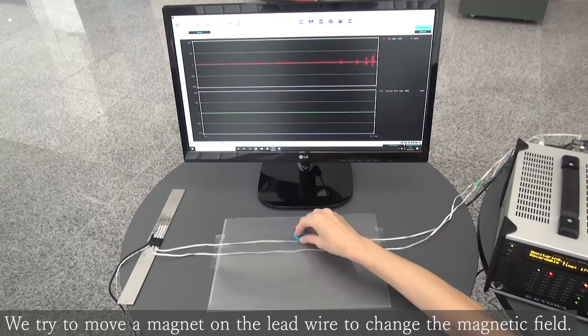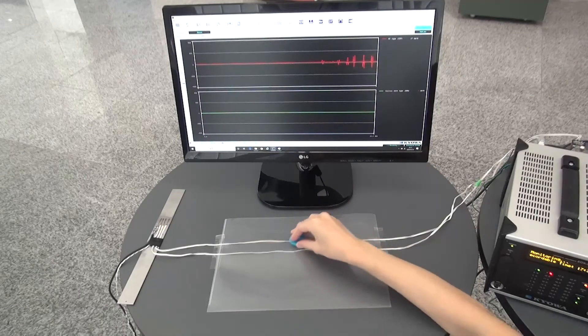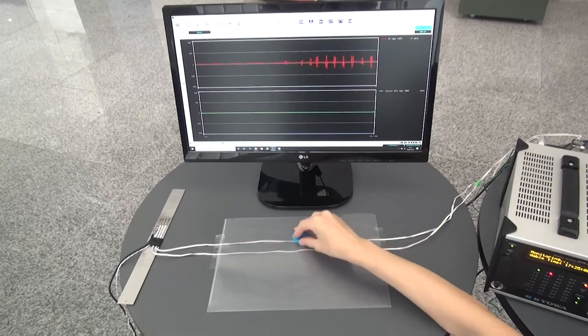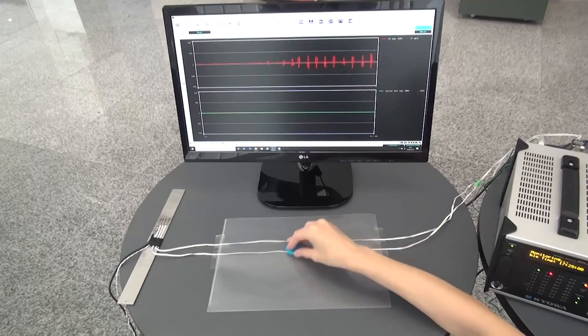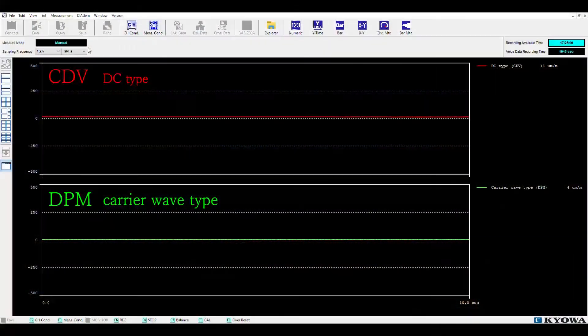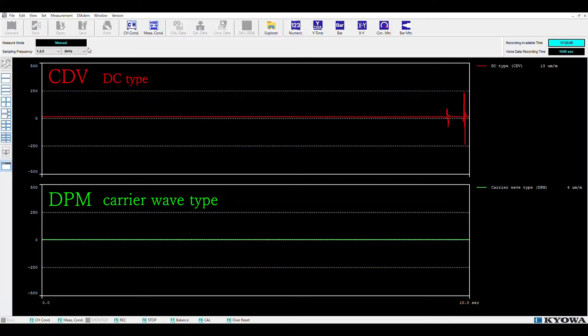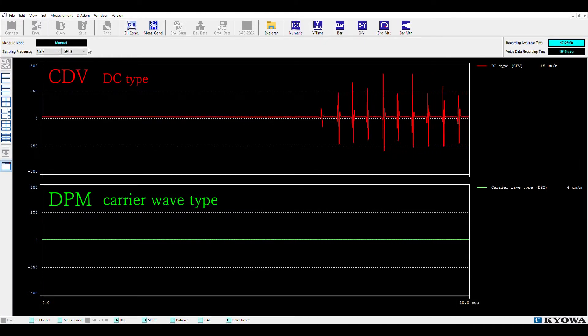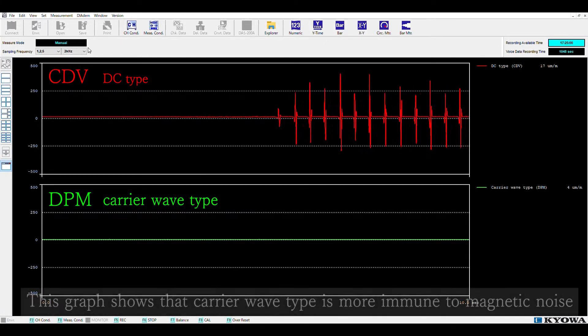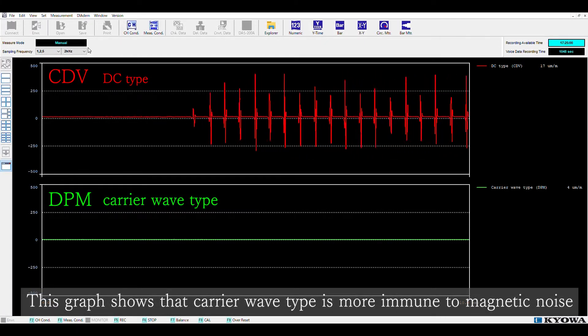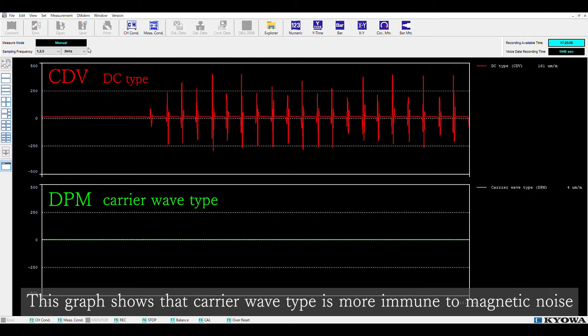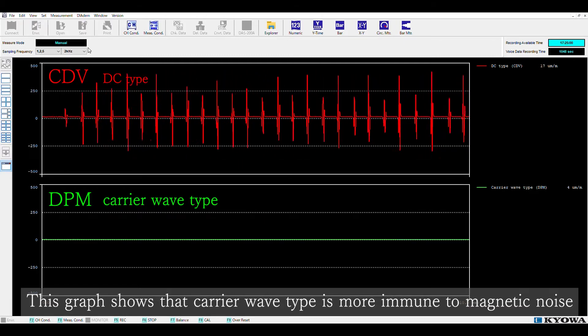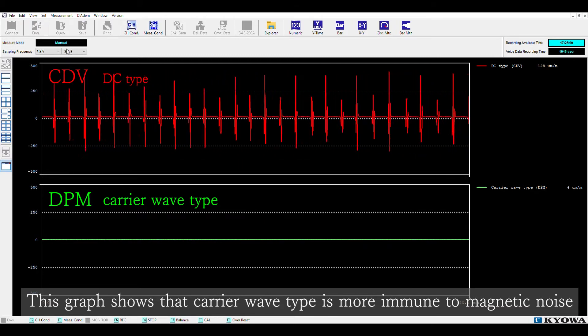When the magnet is moved on both lead wires, it always appears on the CDV side greatly. But we can see DPM is not being influenced by magnetic field. This trial shows that magnetic field does not affect the measurement with carrier wave type amplifier DPM.